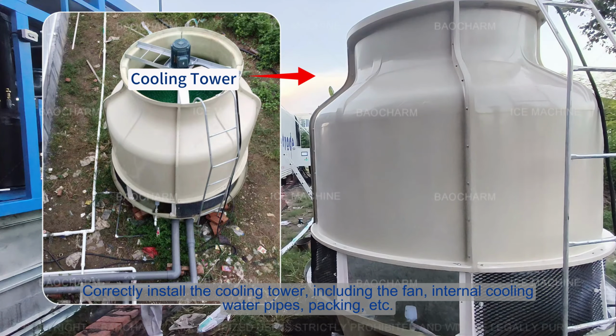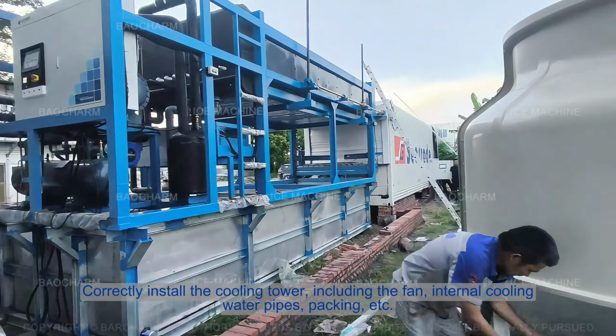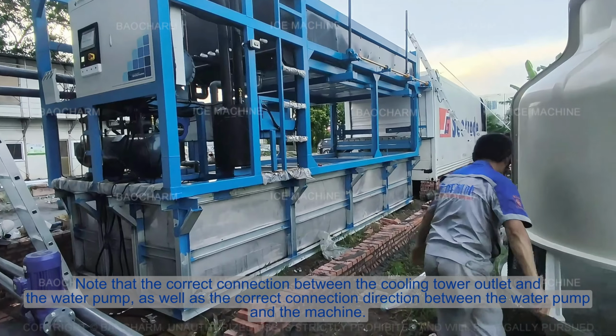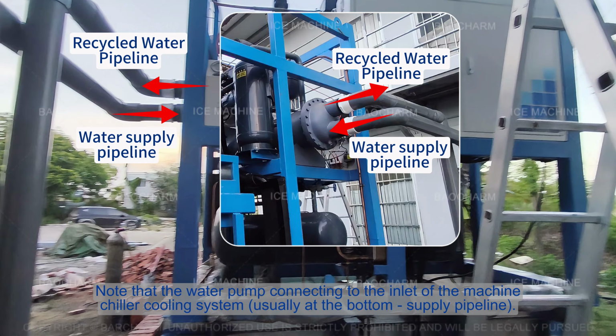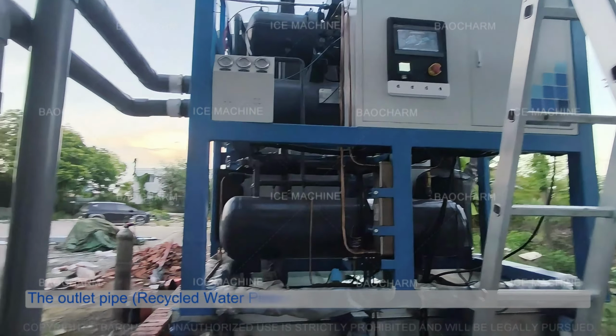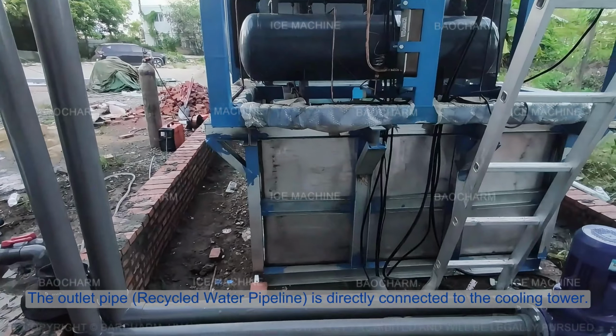Correctly install the cooling tower, including the fan, internal cooling, water pipes, packing, etc. Note the correct connection between the cooling tower outlet and the water pump, as well as the correct connection direction between the water pump and the machine. Note that the water pump connects to the inlet of the machine, the chiller cooling system usually at the bottom supply pipeline. The outlet pipe is directly connected to the cooling tower.